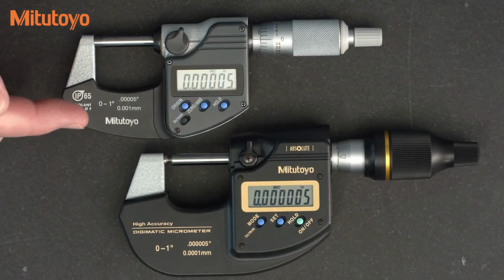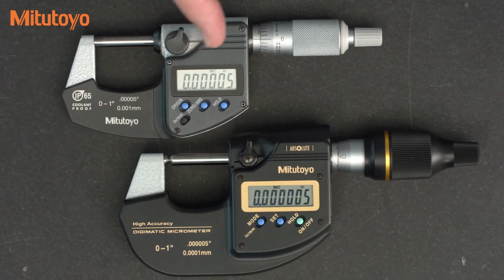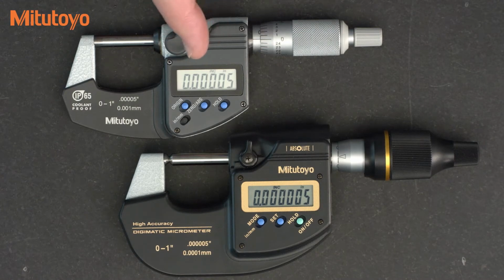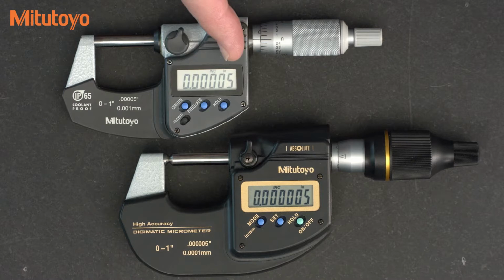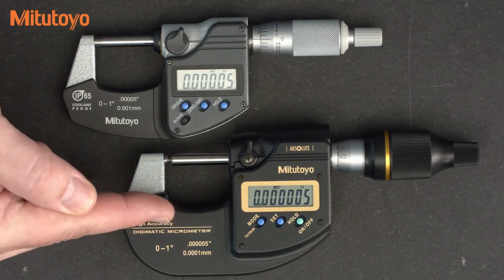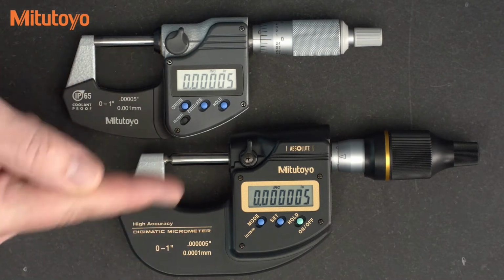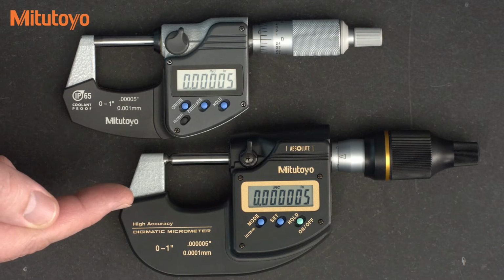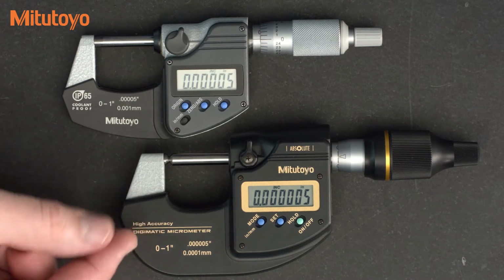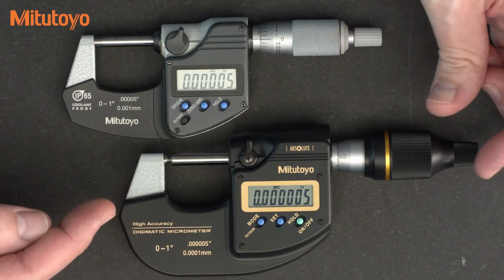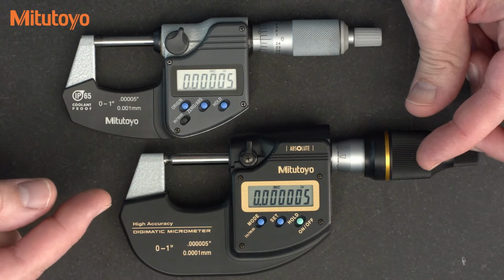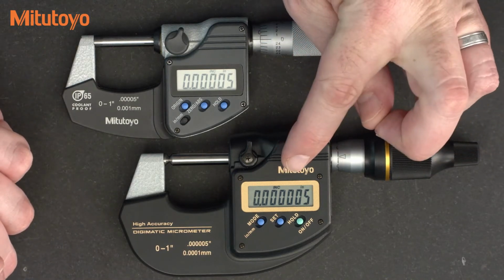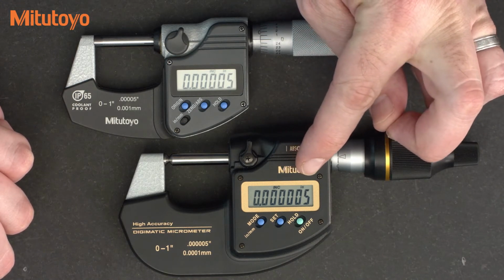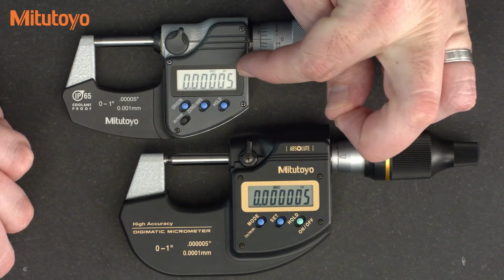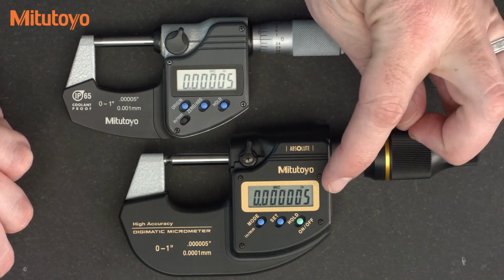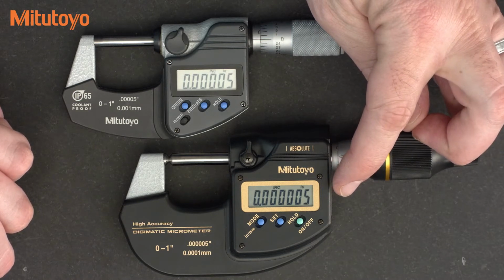This is the common digital outside micrometer with a resolution of 50 millionths of an inch or 1 micrometer. As you can see here, we have 5 decimal places, that's 50 millionths. Now this is the MDH micrometer, which may look the same as any other outside micrometer, but there are a number of critical differences. We have a much more enlarged and rigid frame here, as well as improved measuring force. You couple those with an improved resolution, 10 times better. This is a digital resolution of 5 millionths or 0.1 micron. Again, this is 50 millionths, 5 decimal places. This is 5 millionths, 6 decimal places. So 10 times better resolution.